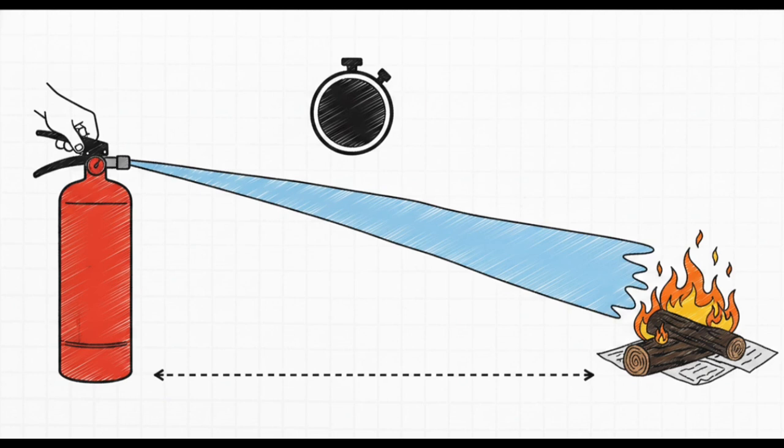Remember our fire classes from earlier? This specific unit is strictly for Class A fires. That means trash, wood, and paper only. Never, ever use this on a grease or electrical fire. It holds 2.5 gallons of water and gives you up to a full minute of continuous discharge. And let me tell you, a minute is an absolute eternity when you're fighting flames.